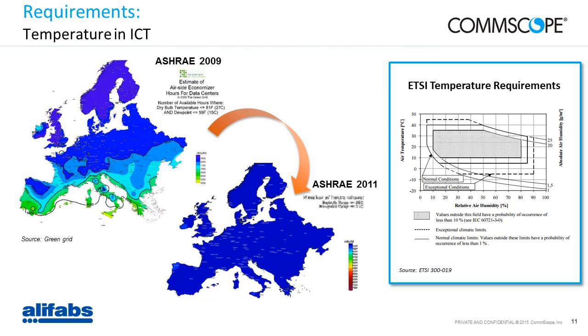Now, in the meantime, the requirements in temperature are changing quite a lot. I've taken a couple of examples of requirements makers, the guys from ASHRAE and from ETSI that I'm sure you all know. ASHRAE dictates the requirements for the data center sites, whereas ETSI is more for the smaller sites. But just to highlight the fact that the thresholds in temperature have widened over the past few years. They have relaxed quite a lot.